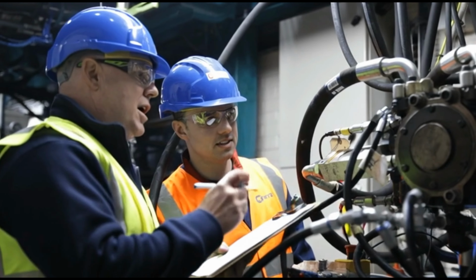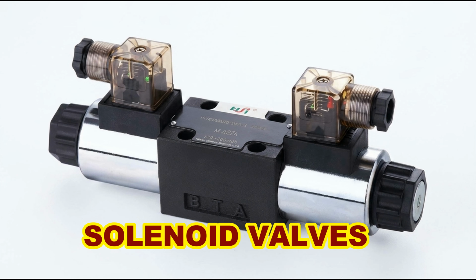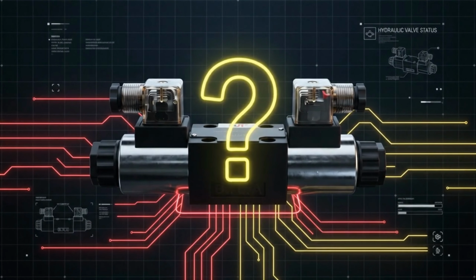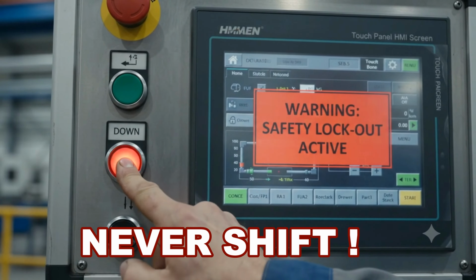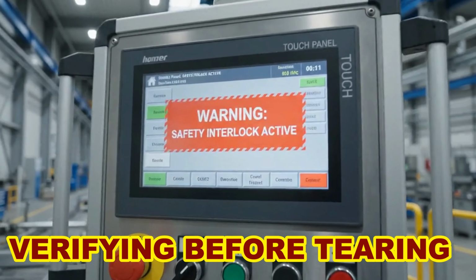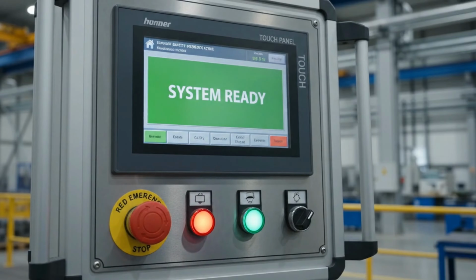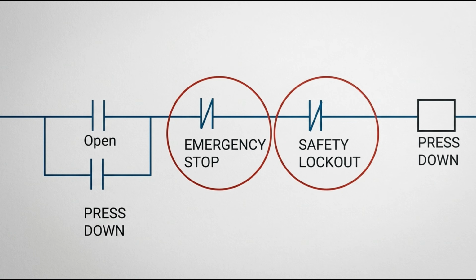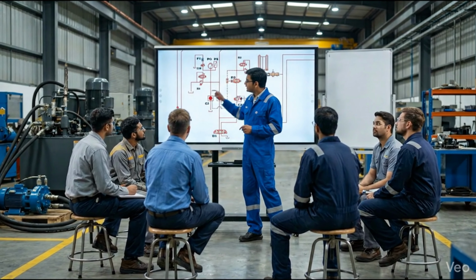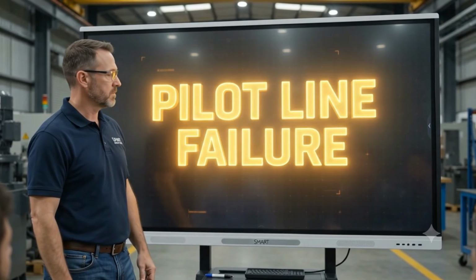In modern systems using electrical solenoid valves, a shifting failure usually comes down to two deadly reasons. First, the valve is simply missing its required electrical signal. Second, a safety interlock has been triggered. If a critical safety condition isn't perfectly met, the interlock system absolutely blocks power to that valve. You can try all day, but that operation will never shift. Therefore, verifying the electrical signal and safety interlocks before tearing into the physical valve is the true mark of a master technician. Now let's talk about pilot circuits and professional conclusions.